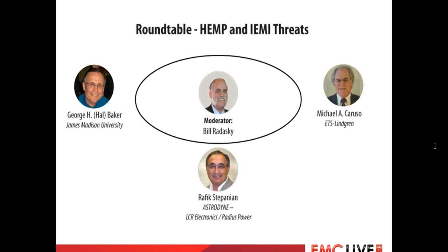Yeah, that's true. I think there are some manufacturers that have overvoltage protection devices, transient overvoltage protection devices, designed to handle both EMP and lightning. Although, as we discussed a few moments ago, the best approach for signal-level conductors is to use fiber connections and deal mainly with the power line, which is the issue we cannot avoid. Now for antennas it's a little different—there you might be able to get away with a single device that does both. But for data lines, you absolutely want to use fiber everywhere.